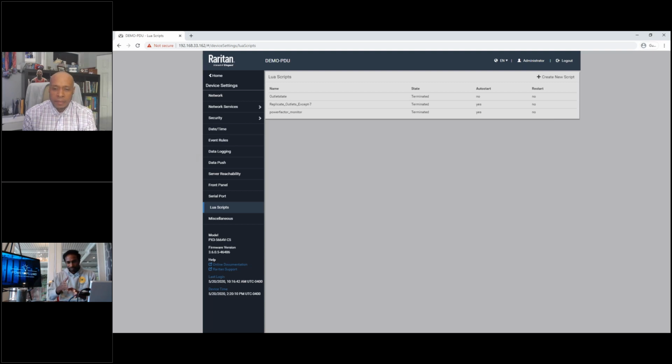And that's why Duncan was talking about how do you now take this to all your PDUs? And those are the methods that he mentioned. One thing that I would also mention is, if you're going to try this on one PDU first, get all the parameters right, because we don't know what the power factor is for your servers and your power supplies.